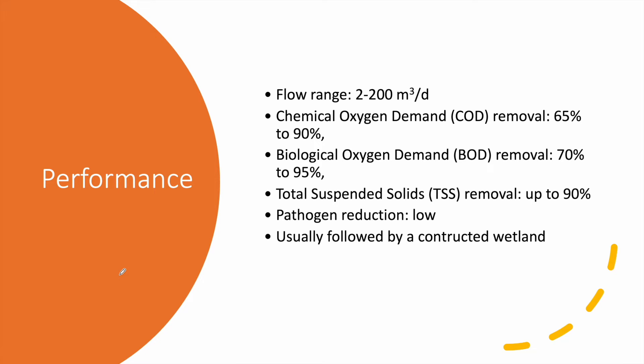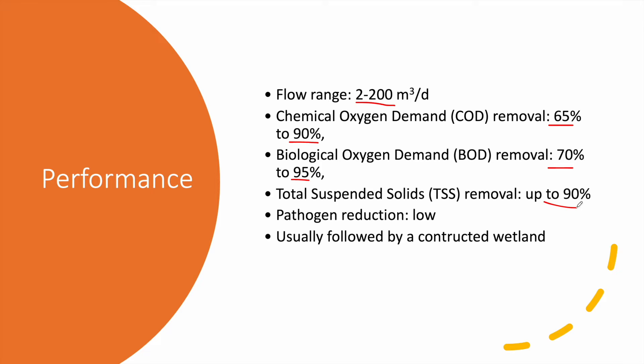An ABR is used for small to medium scale projects with a flow range of 2 to 200 cubic meters per day. It achieves a high removal of organic matter: COD removal of 65 to 90 percent, BOD reduction of 70 to 95 percent, and up to 90 percent removal of total suspended solids. Pathogen reduction is low, so tertiary treatment — disinfection through chlorination or UV — is needed, and the ABR is usually followed by a constructed wetland.